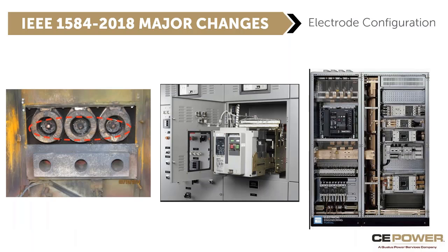So here are some pictures of what that horizontal, more dangerous configuration looks like in the real world. You'll typically see this set up in switchgear with draw out circuit breakers. That is typically where this hazard exists, and that's when you need to adjust accordingly. HCB, as we're going to see in a bit, is always worse than the vertical configurations. So this is what you should be considering.